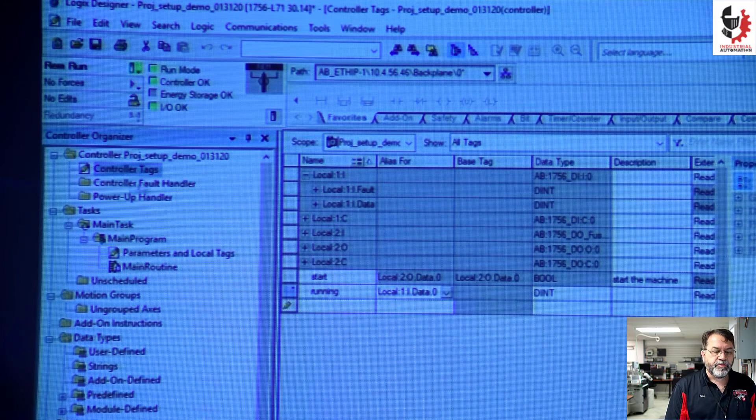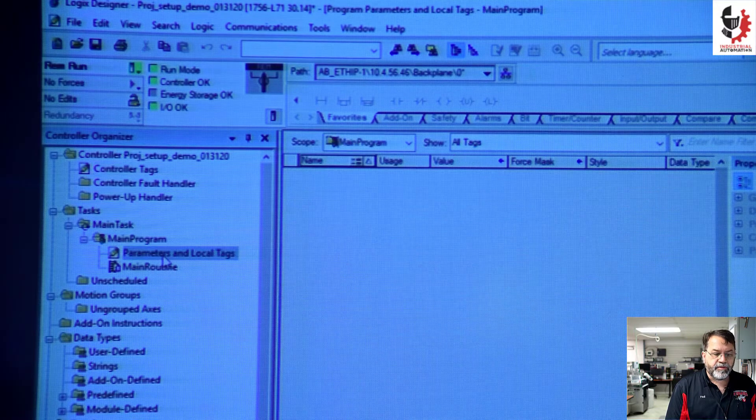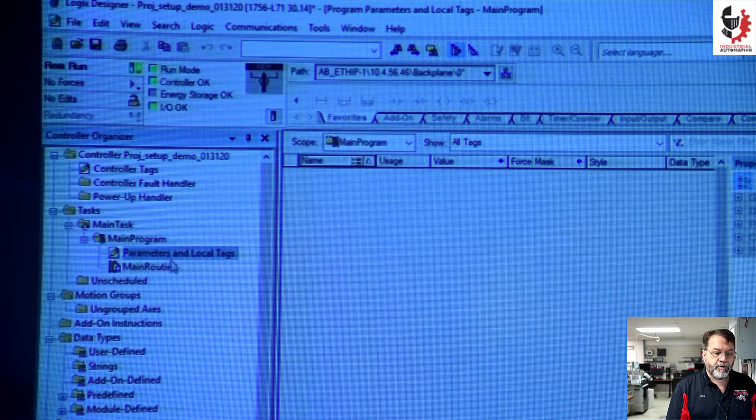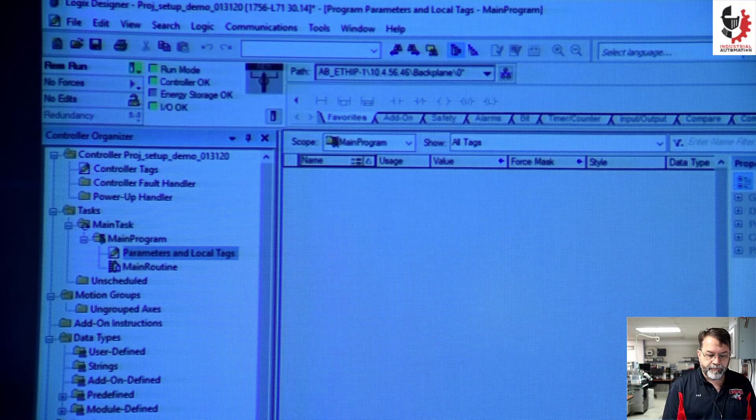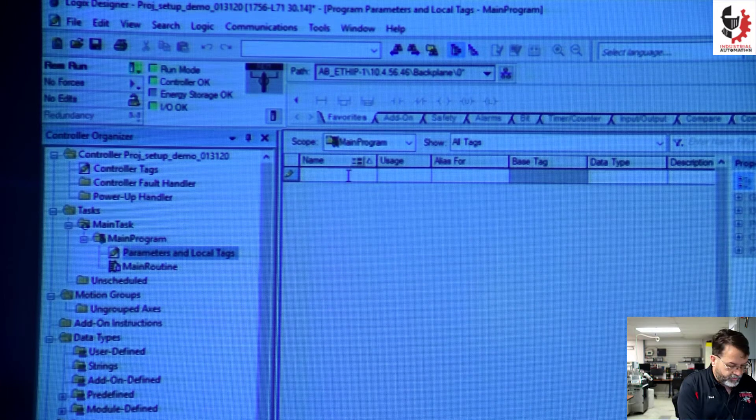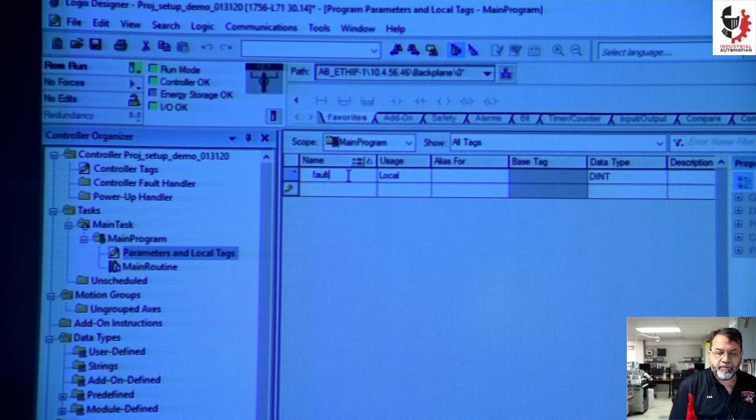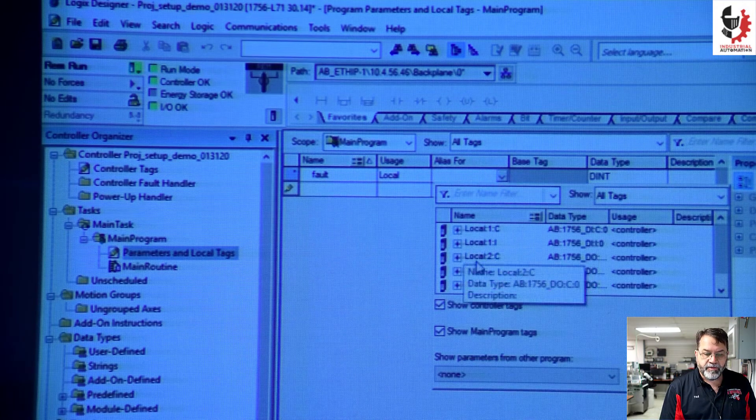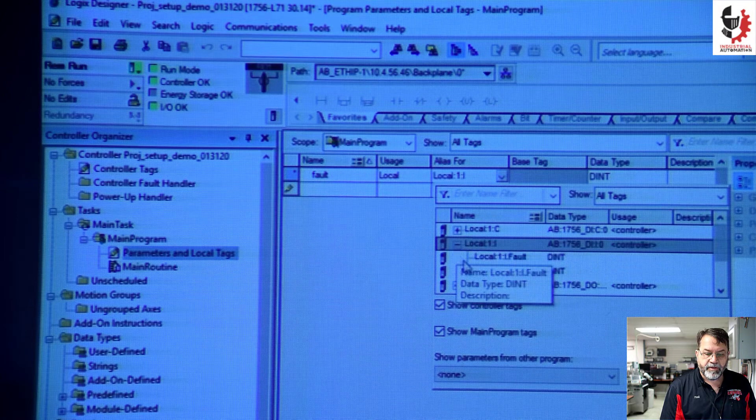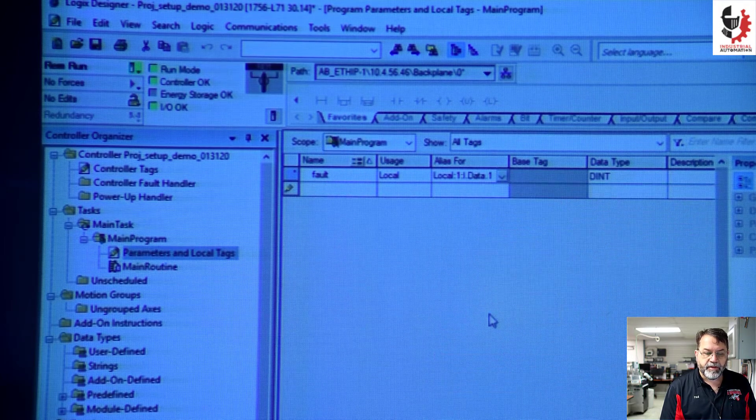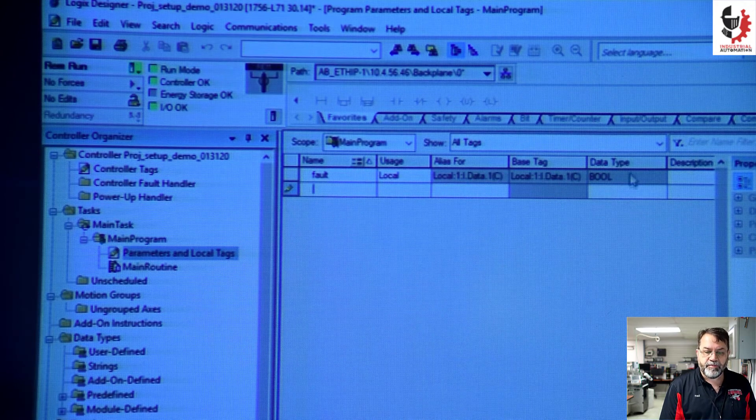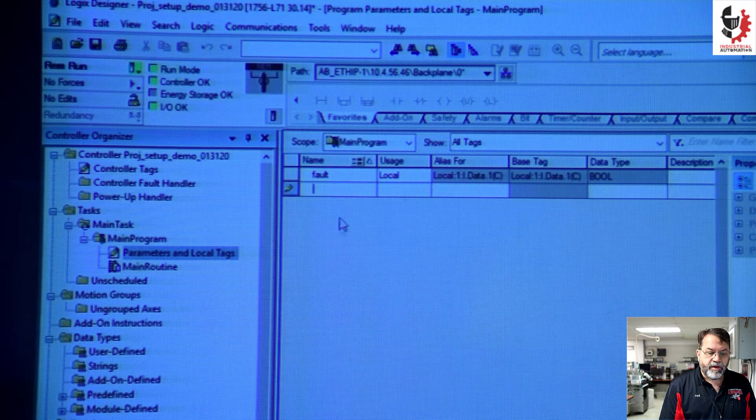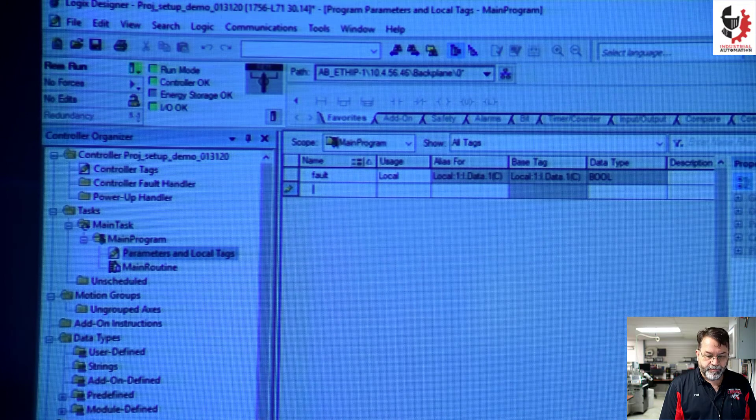So if I go down here to my main program, my tags here, I don't have any tags. Nothing is showing, but I can go to edit tags and I'll make one more. I'll call it fault. And that's an alias for another input. So local one input. And I'll take data one. Again that updated to a boolean.